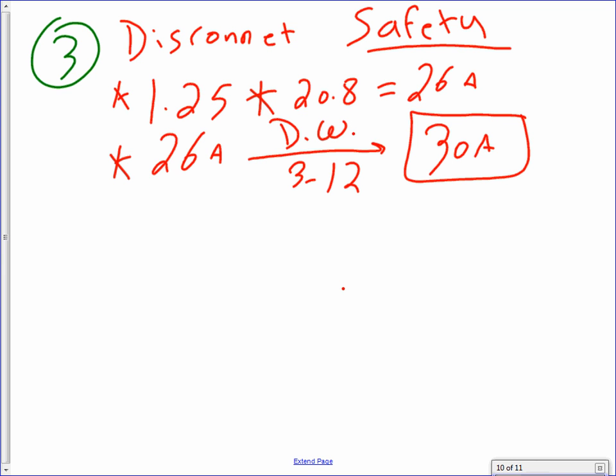Now, can I use the circuit breaker as a disconnect? Absolutely. Do I need a disconnect if the water heater is right next to the panel, within 50 feet of the panel? No, you don't need a disconnect. The circuit breaker acts as your disconnect. When do you need it? You were throwing disconnects all over, right? Why? Anybody know why? Because the panel for the water heaters is not in the same room. They're out of sight. They're not within sight.